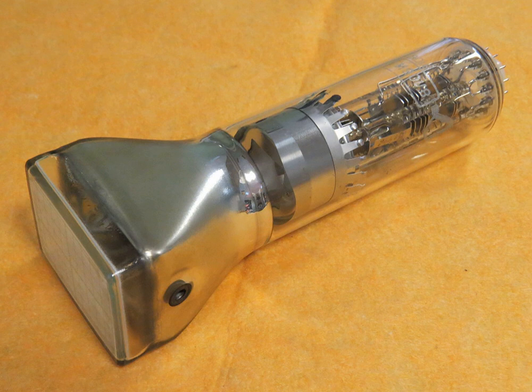Occasionally, an oscilloscope user breaks the ground pin in the power supply cord of a bench-top oscilloscope in an attempt to isolate the signal common from the earth ground. This practice is unreliable since the entire stray capacitance of the instrument cabinet connects into the circuit. It is also a hazard to break a safety ground connection, and instruction manuals strongly advise against it.